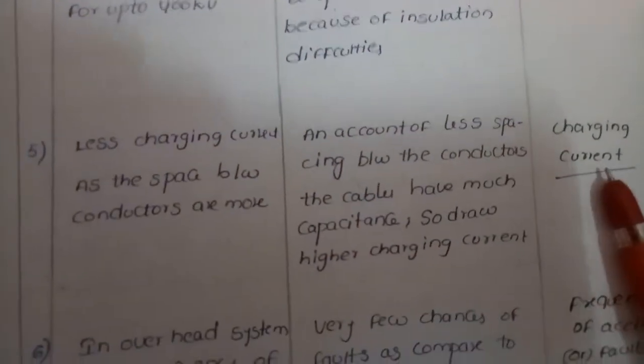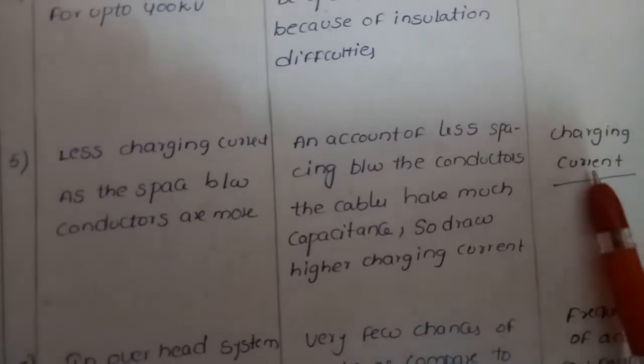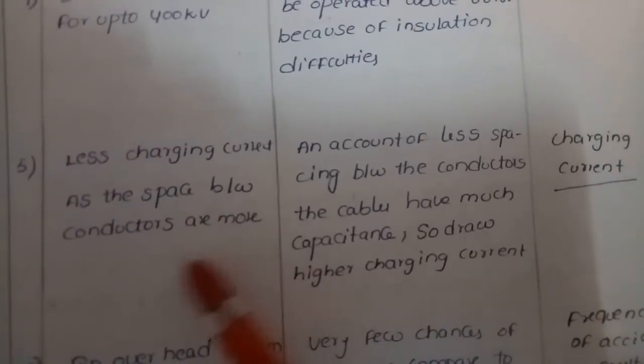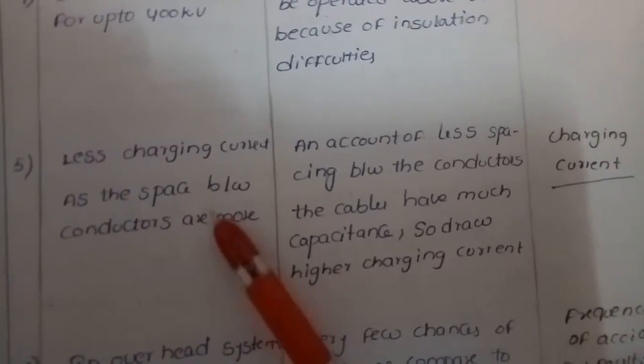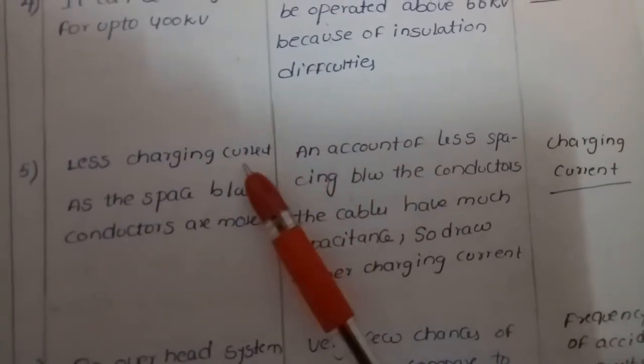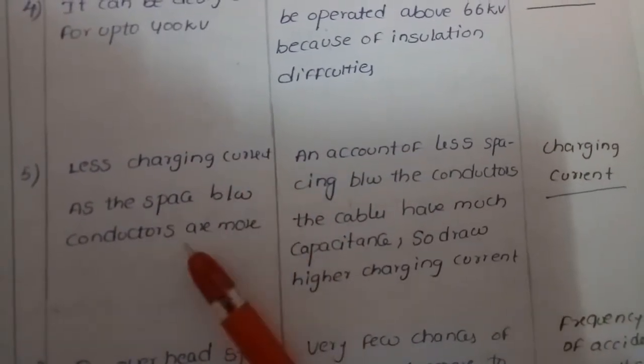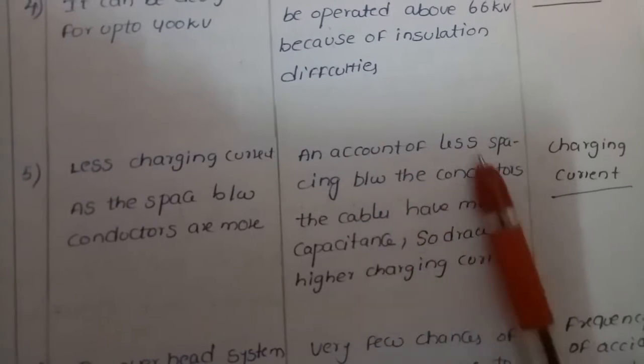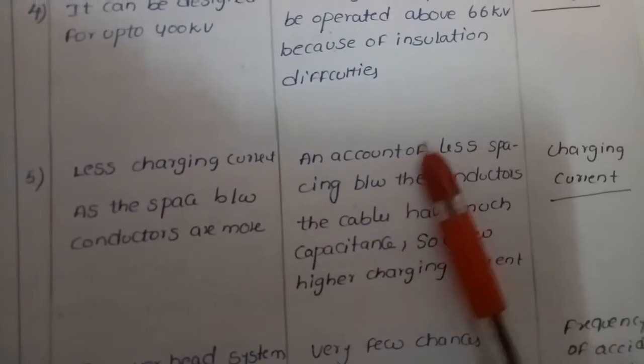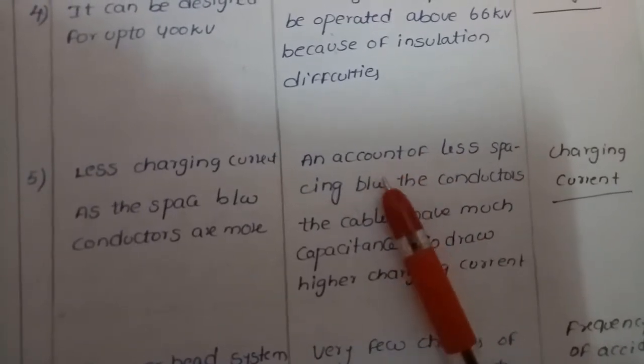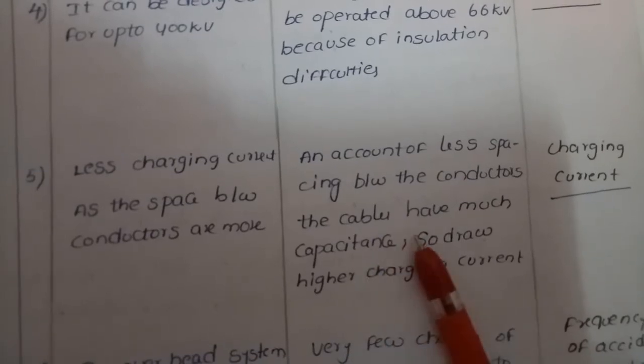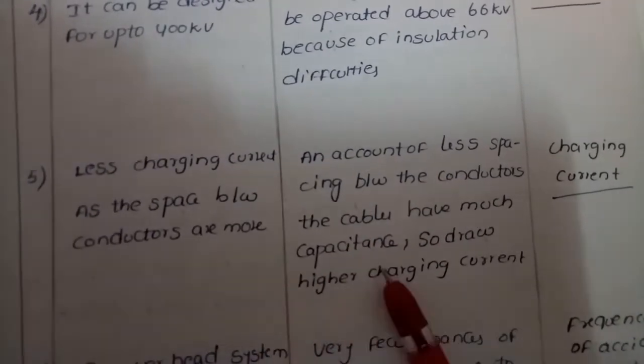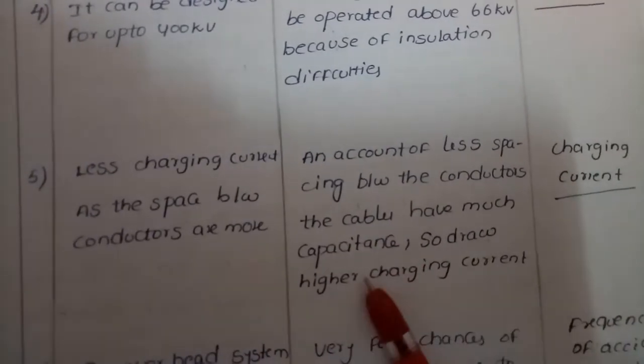Another aspect is charging current. In overhead systems, the spacing between conductors is more, so charging currents are less. In underground systems, due to closer spacing in the cable channel, the cables have much higher capacitance and therefore draw a high charging current.